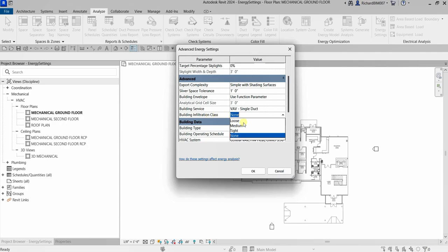According to Revit's help documentation, Loose is 0.076 CFM per square foot for loosely constructed walls; Medium is 0.038 CFM per square foot; Tight is 0.019 CFM per square foot for tightly constructed walls; and None means infiltration is excluded from the calculation of loads.